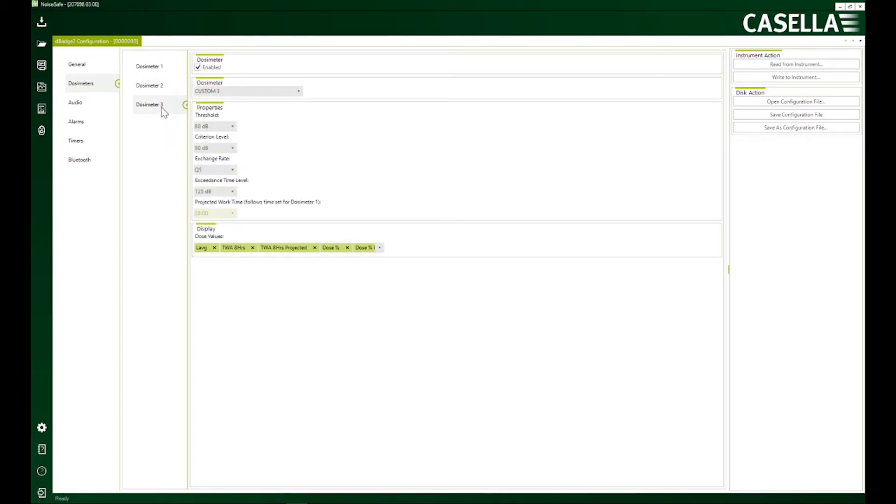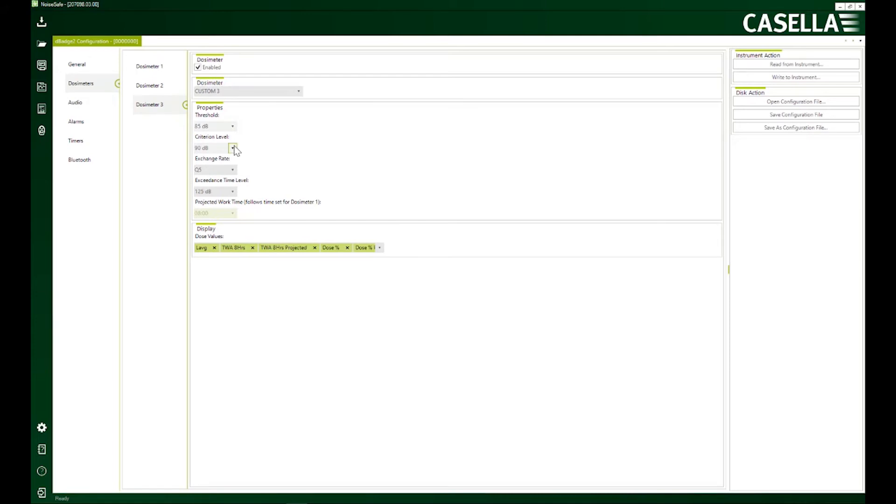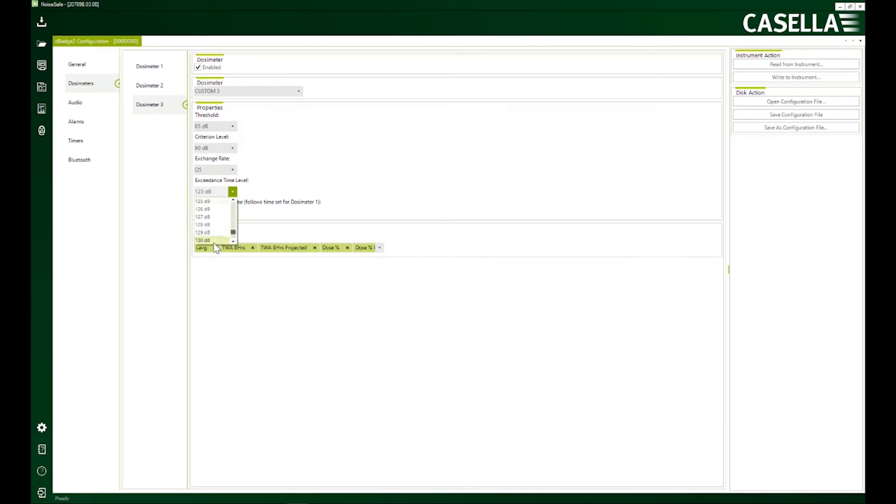I'm going to select dosimeter three to my own personal settings. I'm going to select a threshold criteria of 85 decibels. And criteria is 90 decibels. And exceedance, I would like to have 130 decibels. So these are my own custom settings.